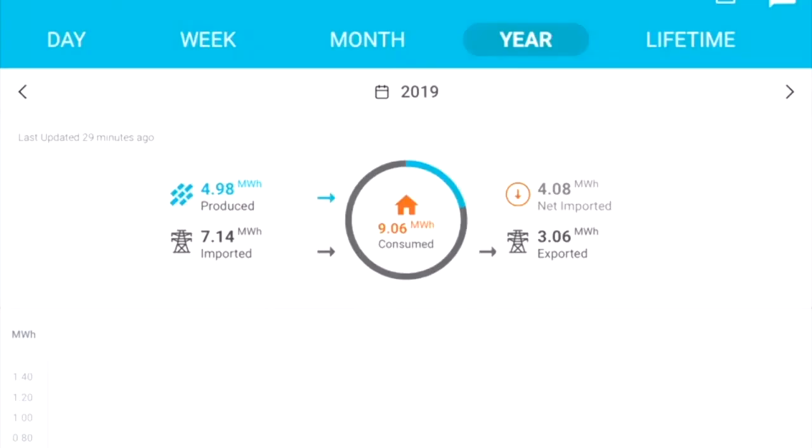Well, they consumed 9 megawatts. A megawatt is 1,000 kilowatts. So basically they consumed 9,060 kilowatt hours, of which just over half was from their solar. So they produced 4,980. And again, be careful to note megawatts versus kilowatts, and remember that a megawatt is 1,000 kilowatt hours.